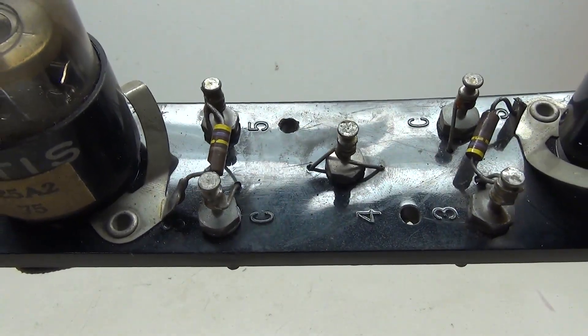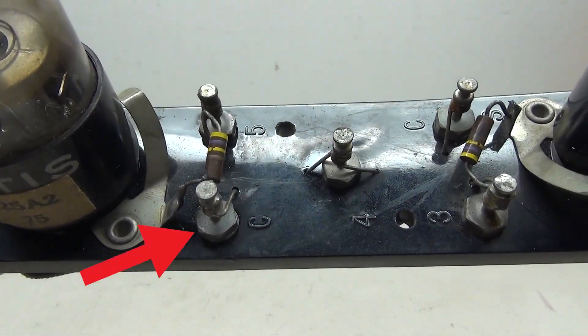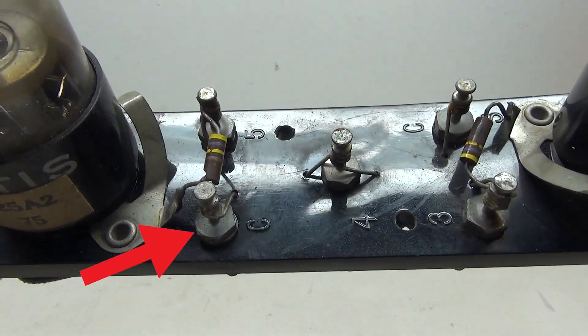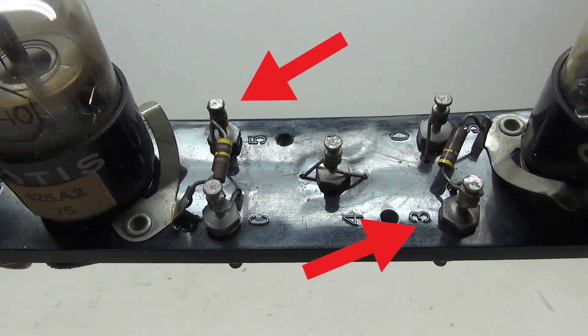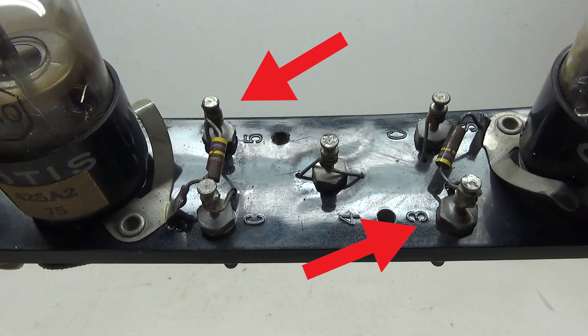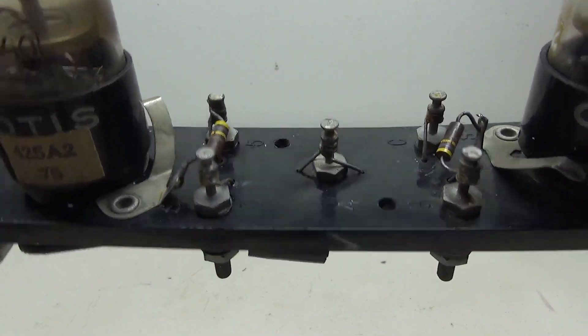As for the actual wiring, you want to place the live wire on the C pin. Now the C pins are separate, so you'll need to connect them together with another wire. And then you'll place your neutral on the 3 or 5 pin, and it doesn't matter which one because they are connected together with a wire.